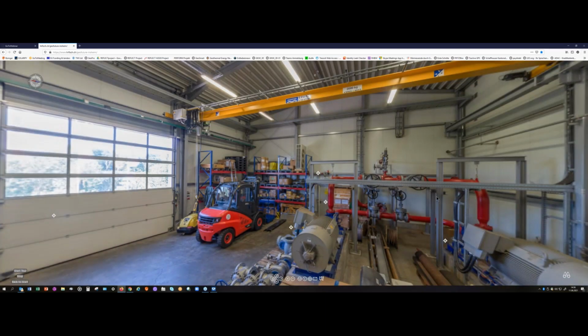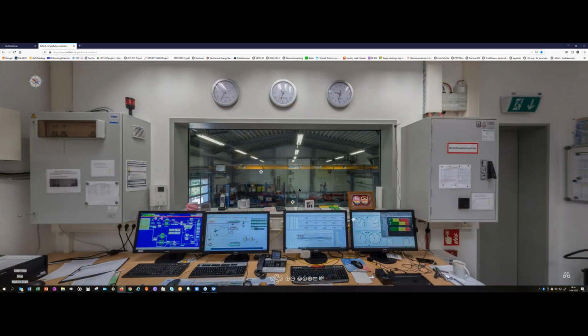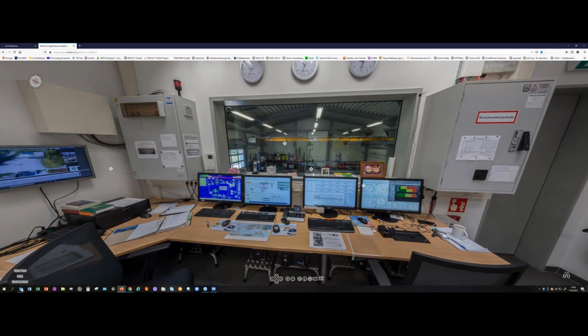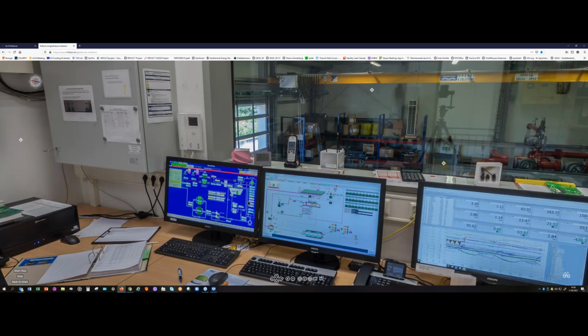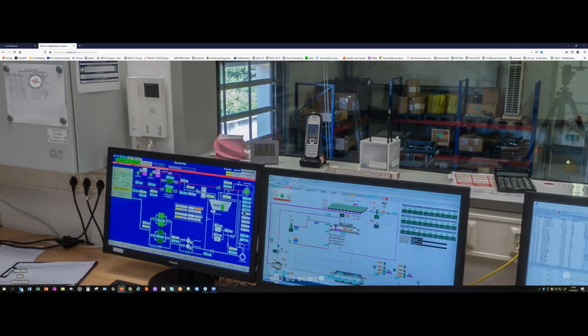In addition to monitoring seismic activity, does the production site monitor groundwater flow and heat during operation? Yes, of course. We monitor not only the flow rate but the temperature of the brine, both on the production and on the reinjection side. We monitor the reinjection pressure constantly over time, and we monitor and record the speed of the motor, so the rotation of the pump.